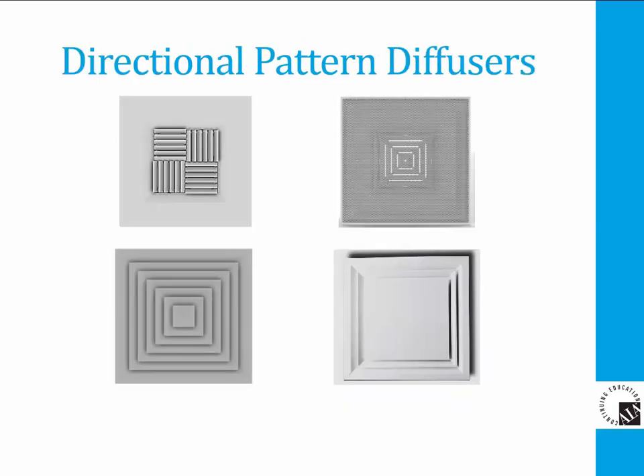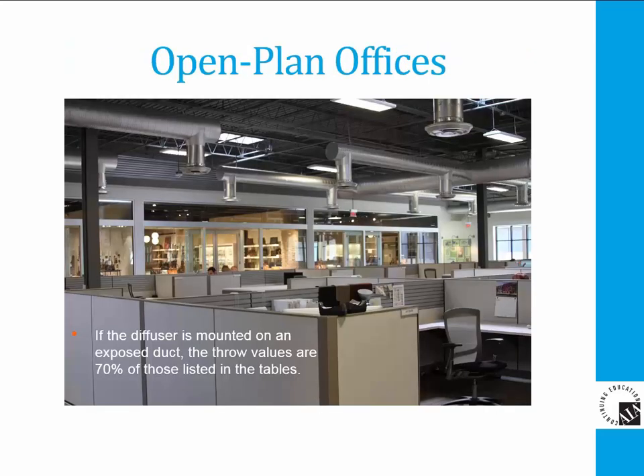The diffusers shown are good examples of units designed to produce a cross flow air discharge pattern. This photo shows how ceiling diffusers with an open ceiling design can be used to condition a landscaped office environment. It should be noted that when the outlet is used in an open ceiling, the distance the air travels to 50 feet per minute will be reduced by 30 percent due to air induction on top of the air jet as well as below.